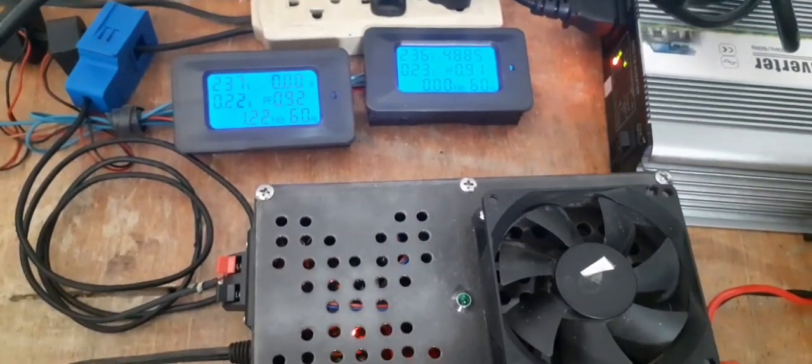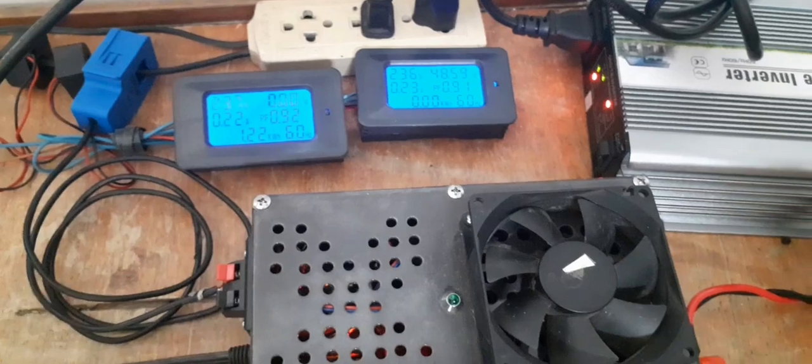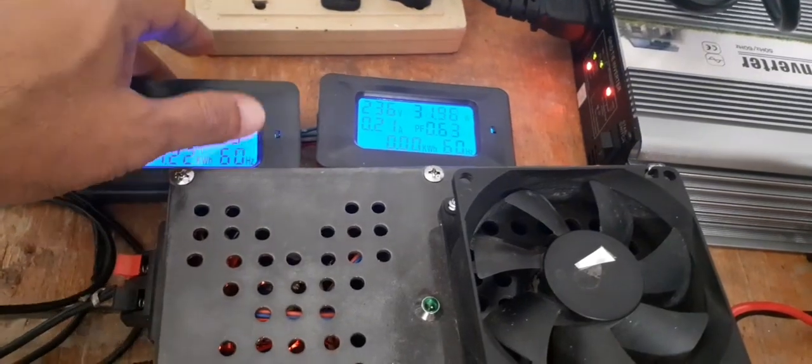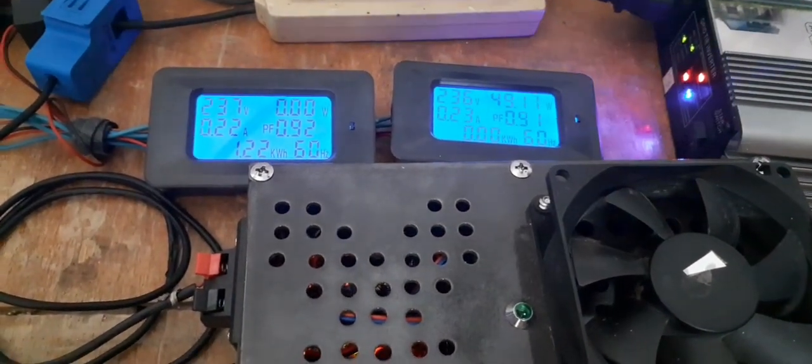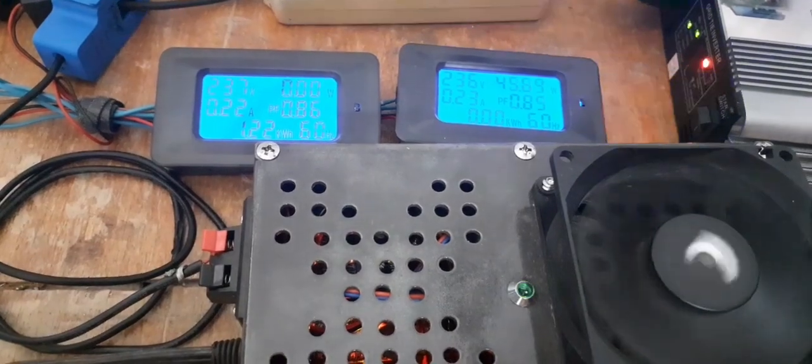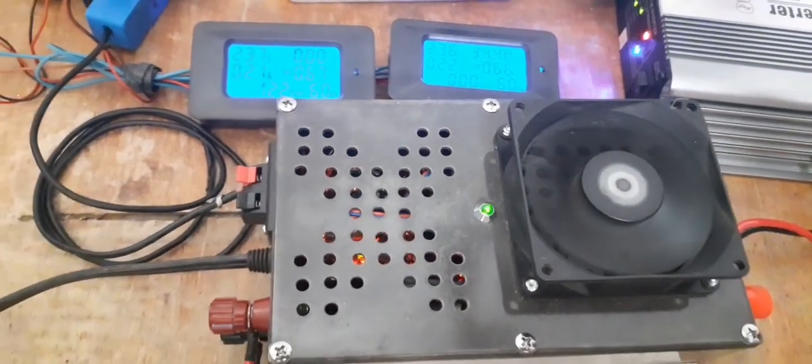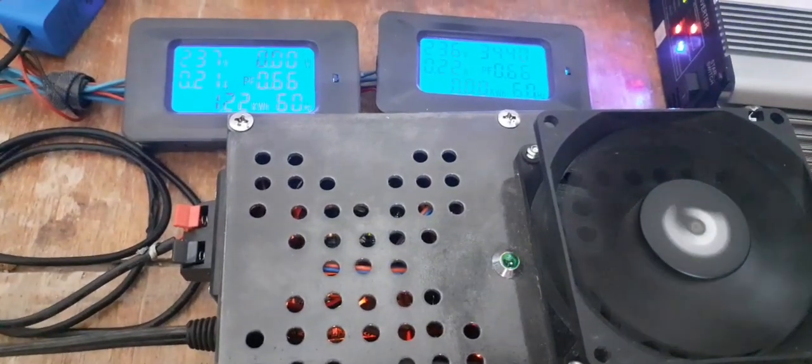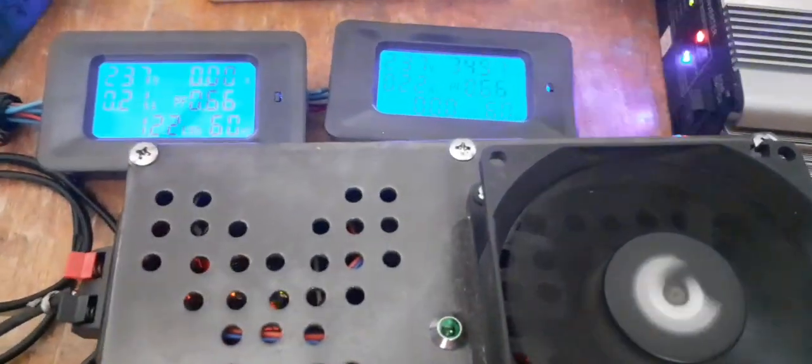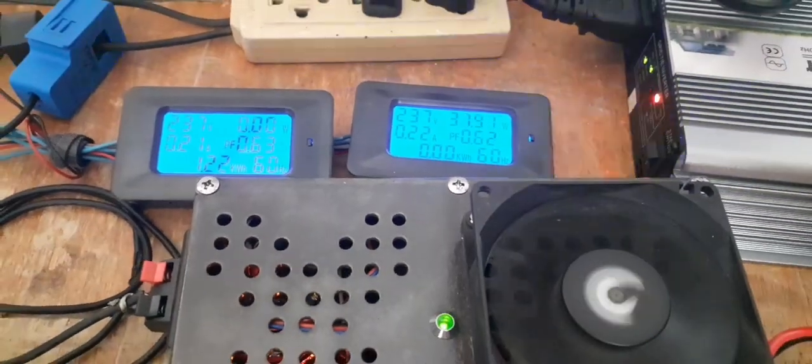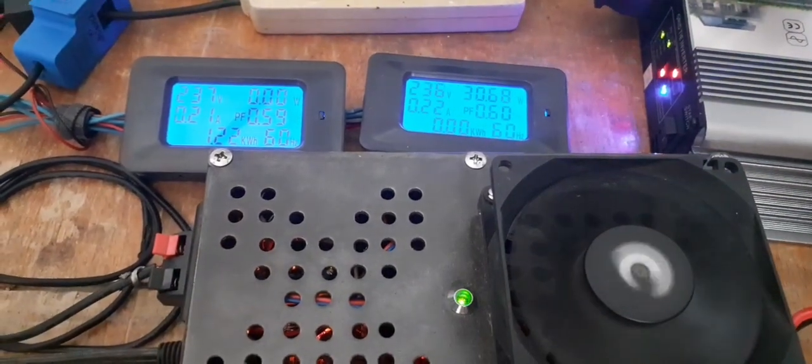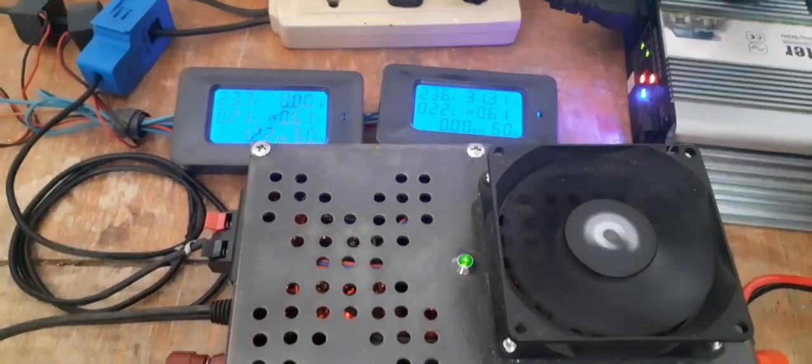The power limiter is giving the inverter some test power output. At the same time, it gets the current transformer signal and then it powers itself up because it detects a load in our system. At this time, the device will try to increase the power output going to the inverter to compensate for the load in our system.